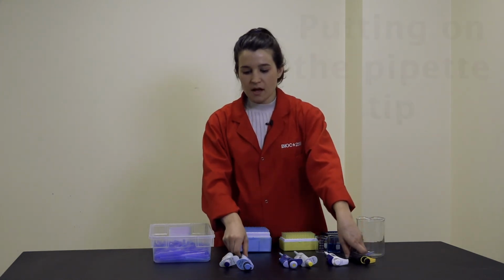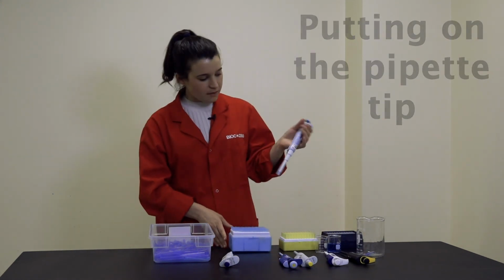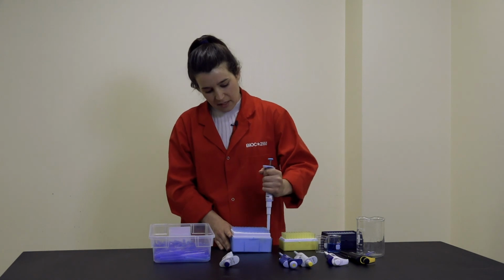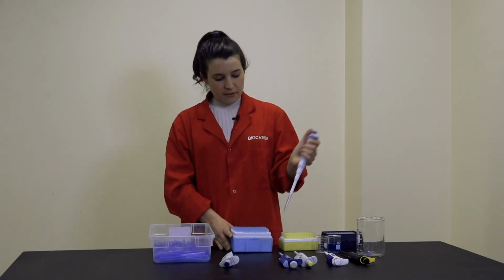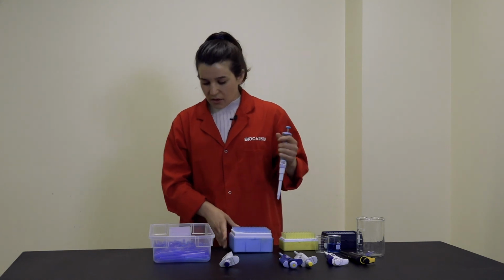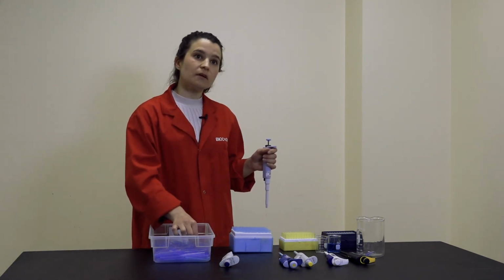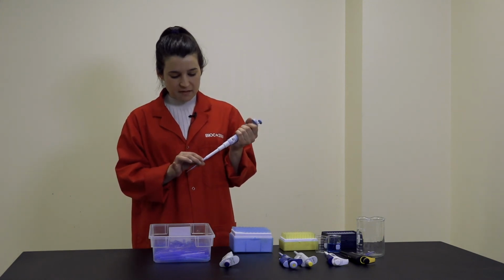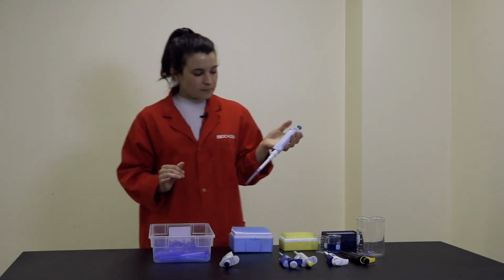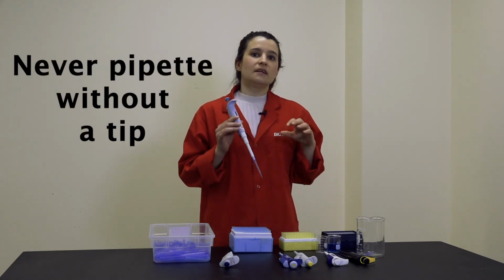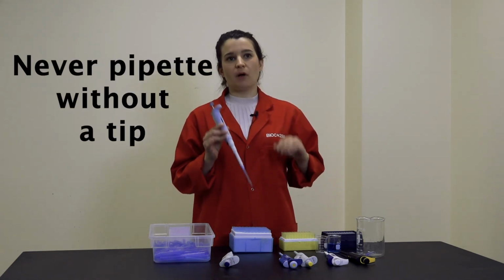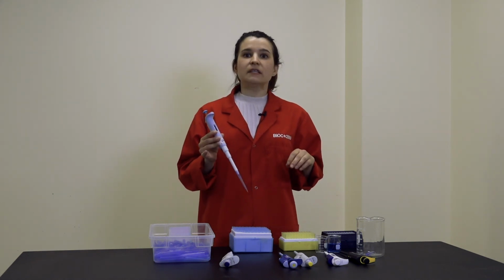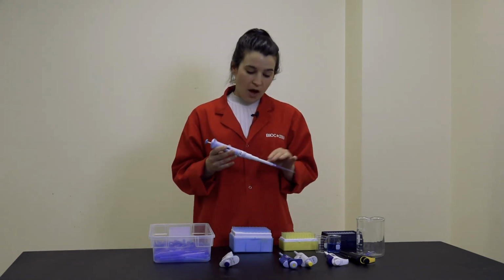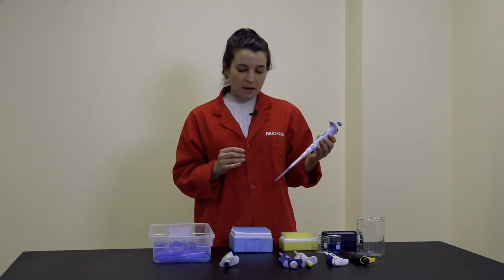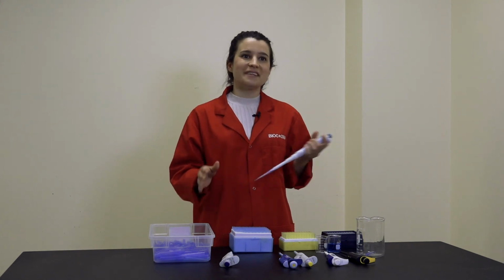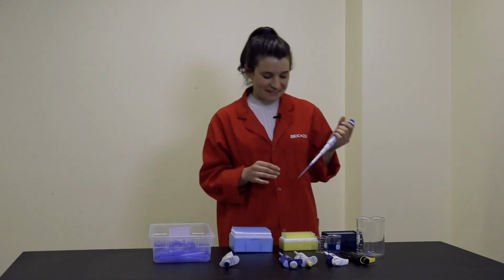So in order to put the pipette tip on, you simply pick up your pipette and firmly place it in the tip and bring it out. Now, in some cases, your lab may use bulk tips. In that case, you just simply pick up the tip like this and put it firmly on like that. So again, you can never, ever pipette without a pipette tip on. This will most certainly damage the pipette. It wouldn't work very well, and you would also contaminate the solution that you're pipetting.